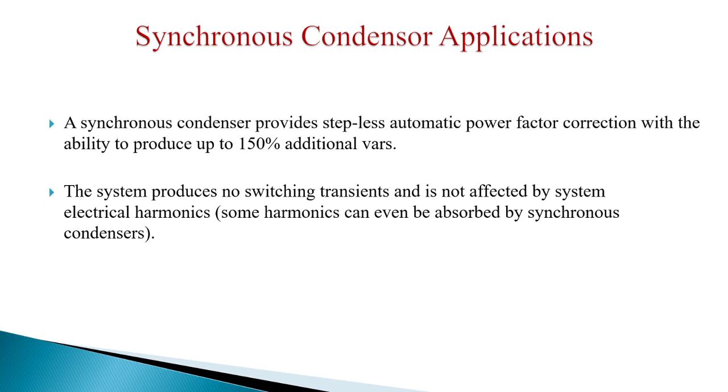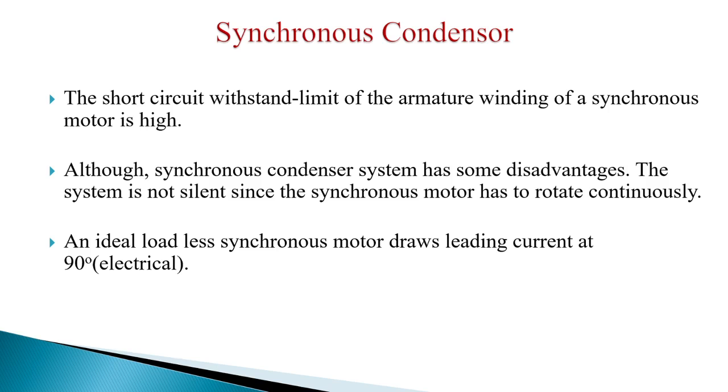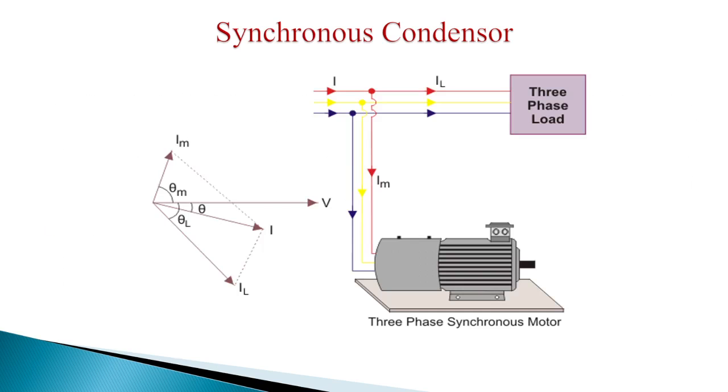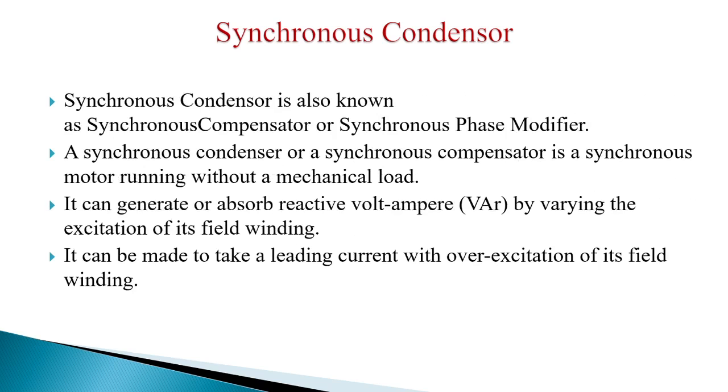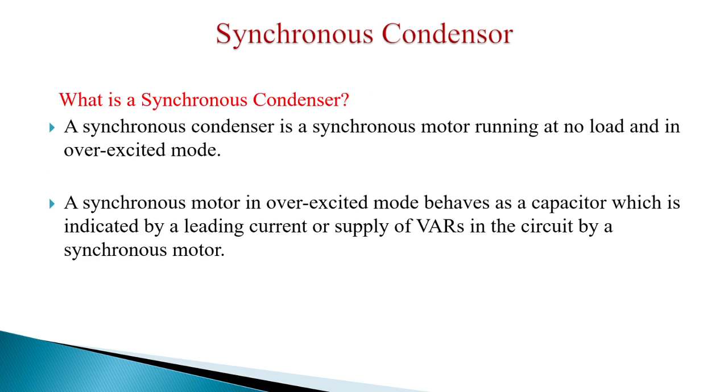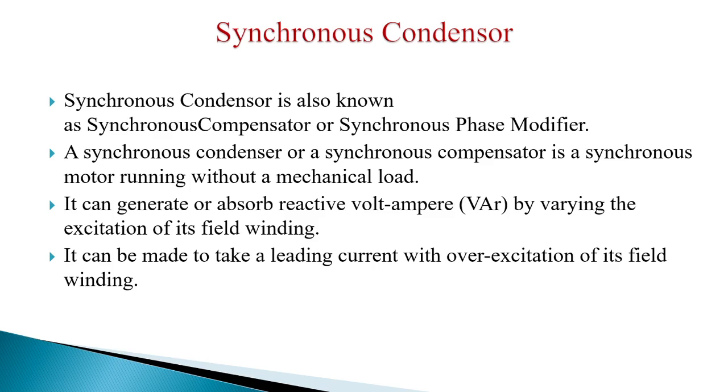So in today's class we have studied the synchronous condenser and its applications. So what is a synchronous condenser? A synchronous condenser is a synchronous motor running at no load and in overexcited mode. In overexcited mode, it will behave as a capacitor, which is indicated by a leading current or supply of VARs in the circuit by a synchronous motor. A synchronous condenser is also known as a synchronous compensator or synchronous phase modifier. It is a synchronous motor running without a mechanical load. It can generate or absorb reactive volt ampere by varying the excitation of its field winding.